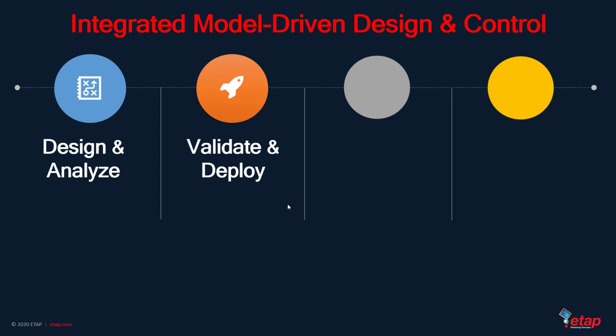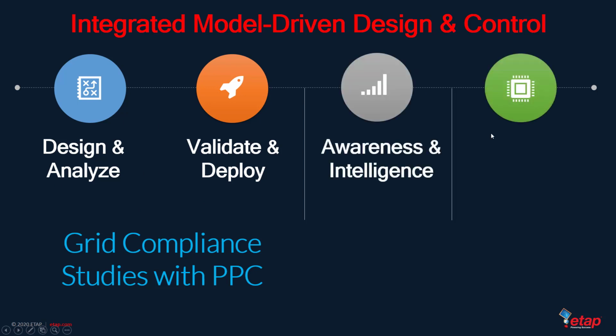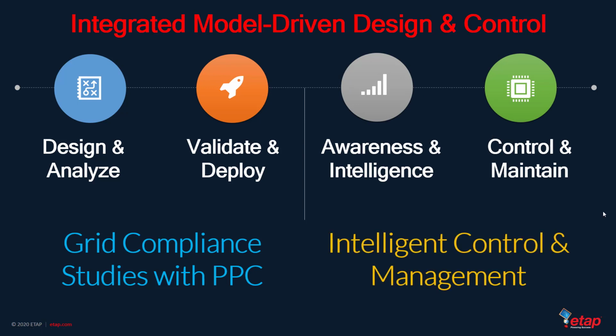These studies provide a greater understanding of the plant behavior under incidents that are internal or external to the system or due to set point changes in the outgoing active power, reactive power, or power factor, and any other disturbances. Mirroring the controller logic between design and operation phases together with intelligent and secure power plant controller hardware ensures reduced commissioning time, compliance with local grid code and standards, as well as a smooth generation plant operation.